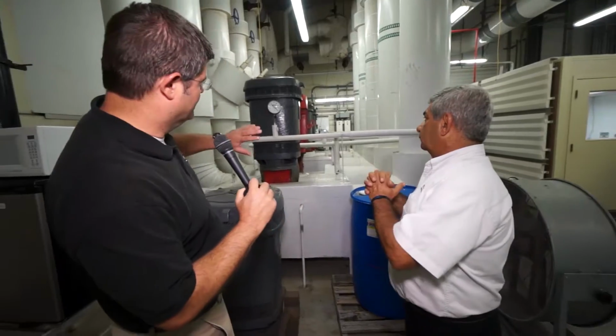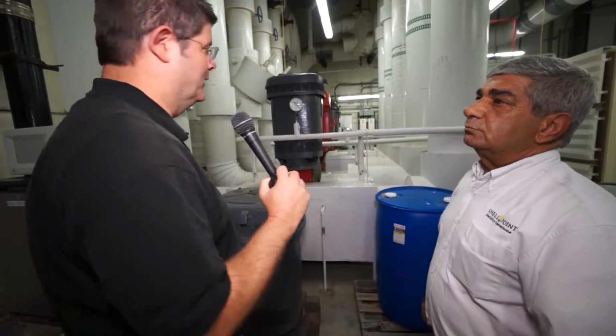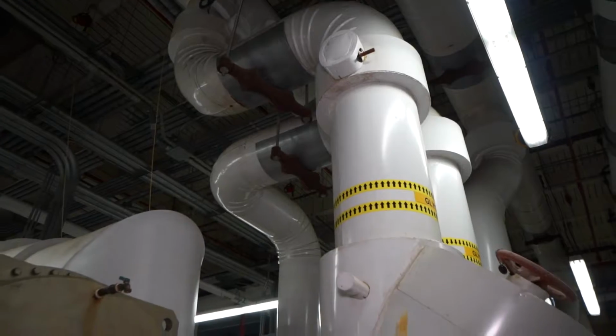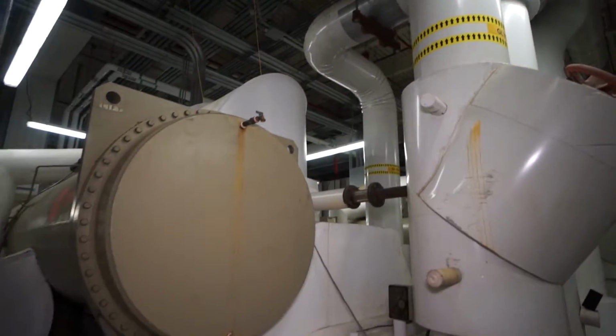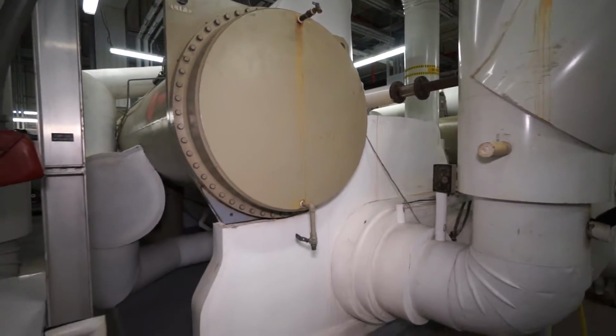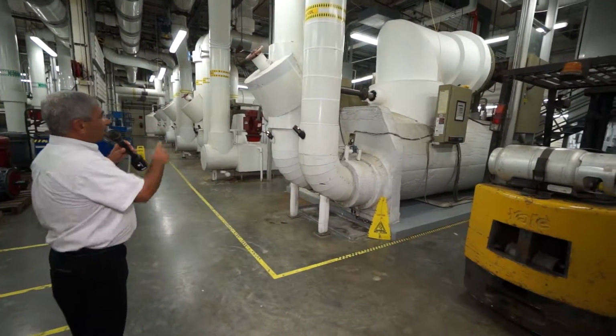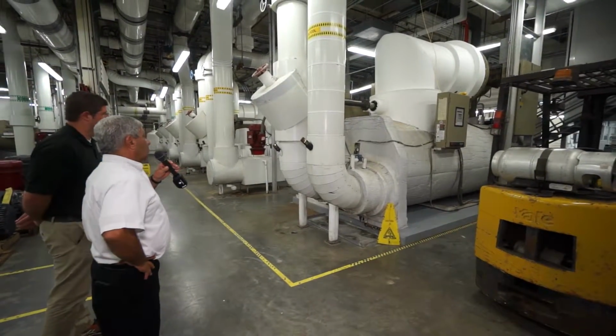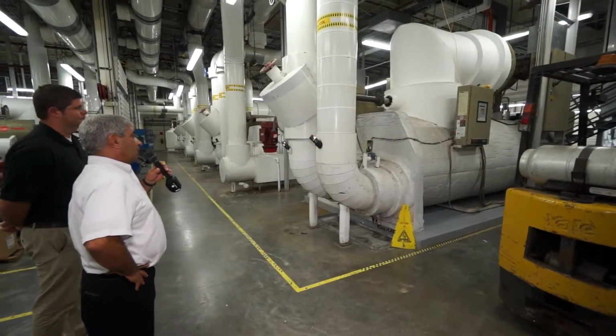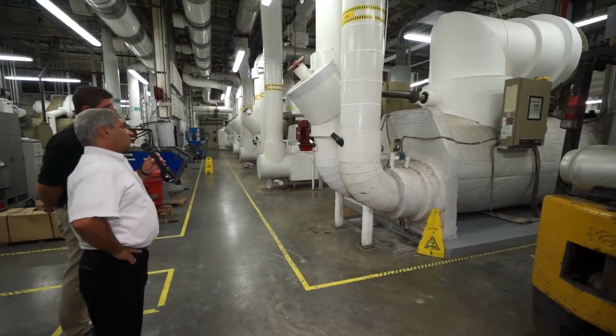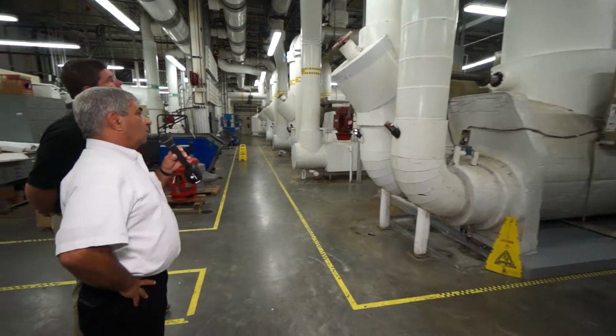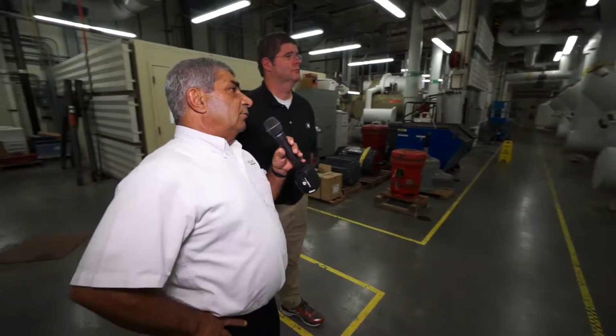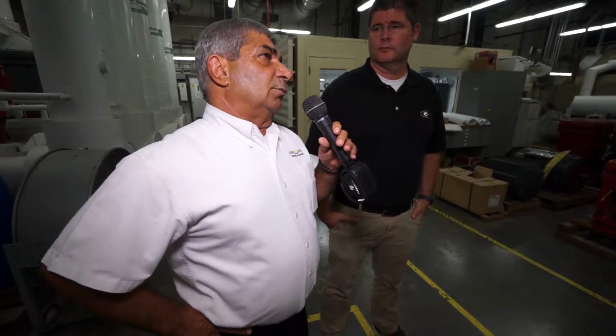Okay, so these pumps are sending everything out to the different communities. What happens next, where do we go now? Okay, the first chiller we're coming to now is one of our dedicated ice chillers, and the next 2 following it are also dedicated, their sole purpose is to make ice. They are each 1,200 tons, and all 3 of them running from 9:30 this evening when we shift our load to approximately 8 a.m. in the morning will freeze all 240 ice tanks out back.